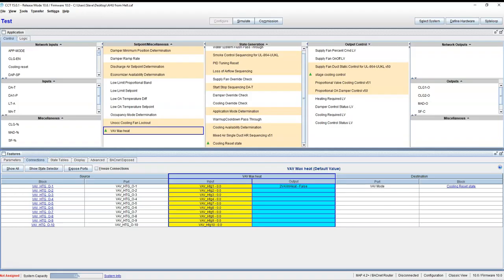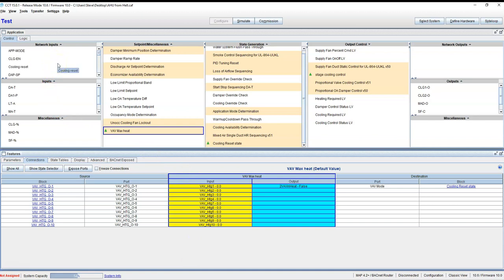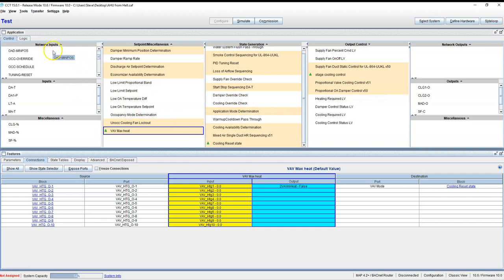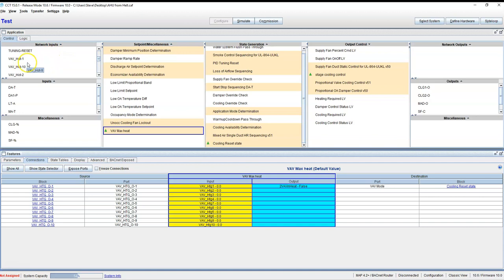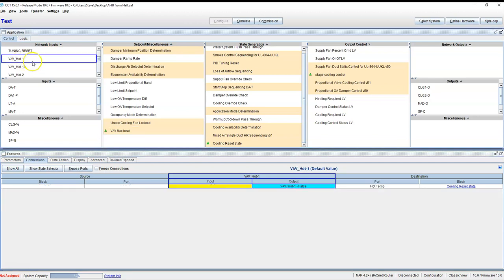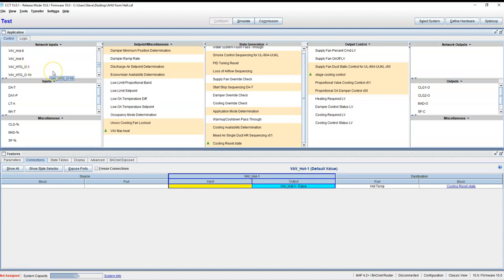Starting with network inputs: we made VAV Hot 1 through VAV Hot 10. That's going to be the alarm coming in from the VAV to say that it's 100% open and the room temp is above set point for over five minutes.